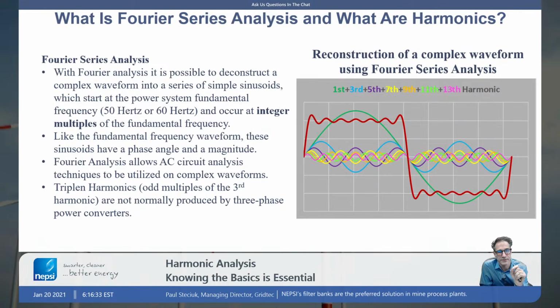We do it at 120 hertz, which is, well, we're going to go with 50 hertz system since we're talking Australia. So the fundamental frequency, remember, is 50 hertz. Second harmonic is 100 hertz. Third harmonic is 150, right? Fourth and so on is 200 hertz. So we're going to create a network model for each and every frequency in the network for each and every harmonic. And harmonics are integer multiples of the fundamental, which is 50 hertz. So we're able to then use standard network analysis that we would have done in college at each and every frequency.